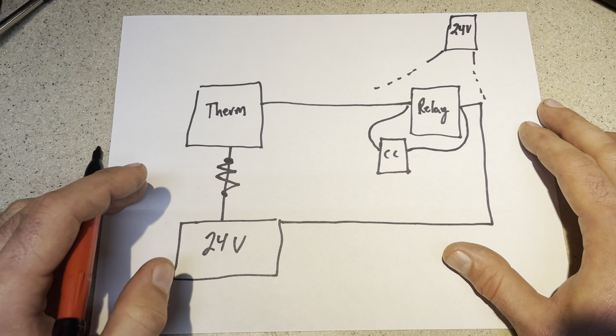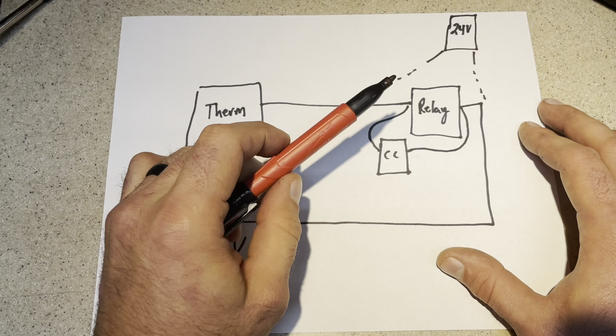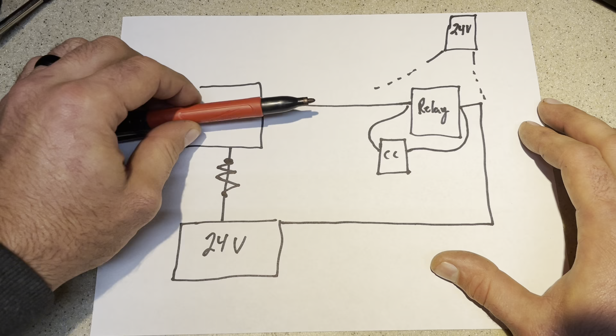Well, we keep our load in place. Loaded circuit tests are always the best kind of test to do on an electrical circuit, as long as you can do it safely. I've got a test light I modified for 24 volts AC that I'll use for this, so I don't have to rig up a contactor or anything. We want to keep our load on there because we want there to be flow, not like a capped garden hose. We want the electrons to be able to move freely in the circuit.